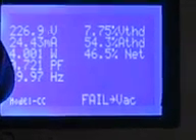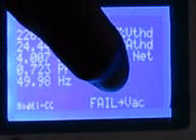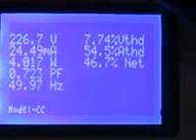Here you can clearly see the model number which is under test, and here is the test result, which is currently showing fail because the voltage AC is beyond the limit. Now, if you want to see further harmonics, you have to press next page.